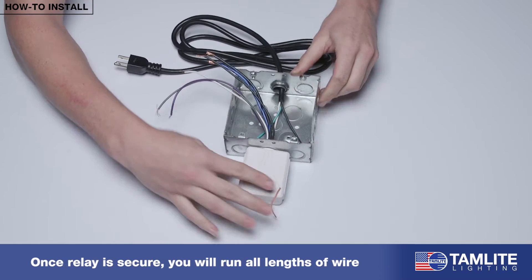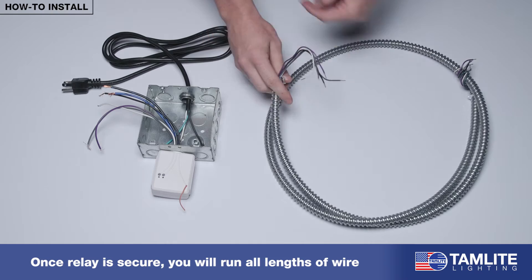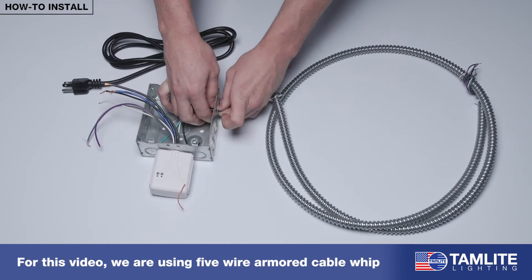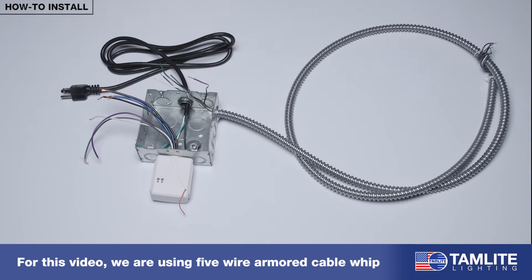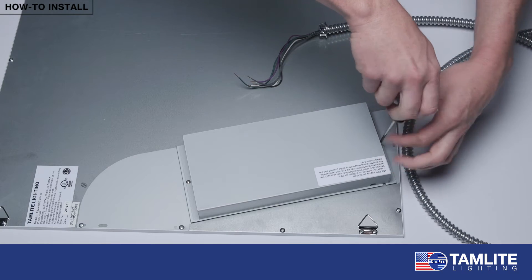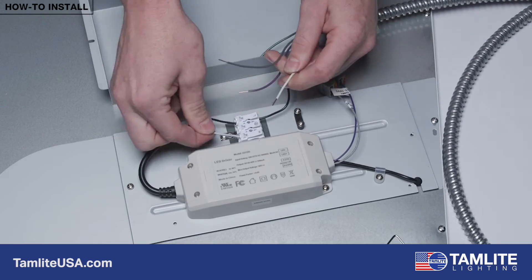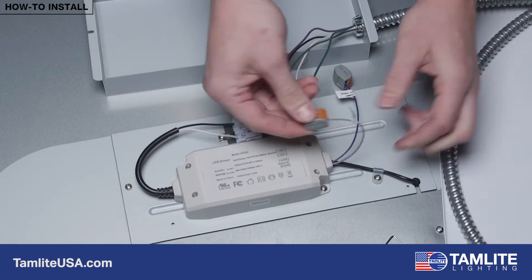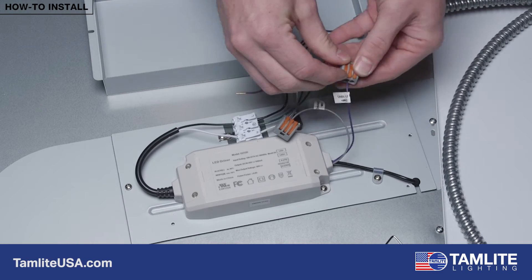Once the relay is secure on the box, you will have to run all lengths of wire, both power and low voltage, from each fixture to your relay. For this application, we are using a 5-wire armored cable whip to run our connections from the fixture to the relay. We've gone ahead and attached our armored cable whip to our junction box where our relay is mounted and connected our wires from the whip to the power supply within the fixture. We can now begin making the required connections within the junction box.